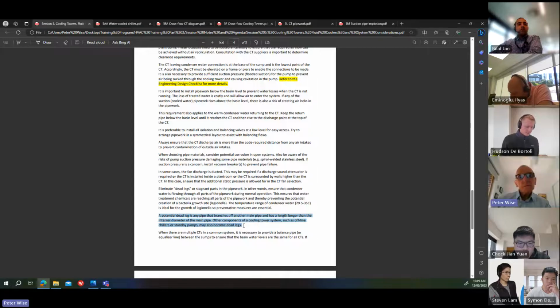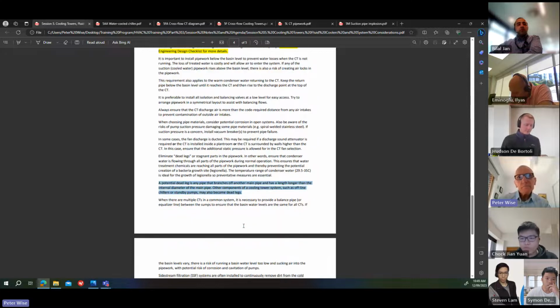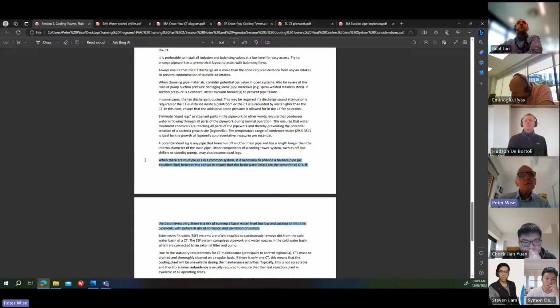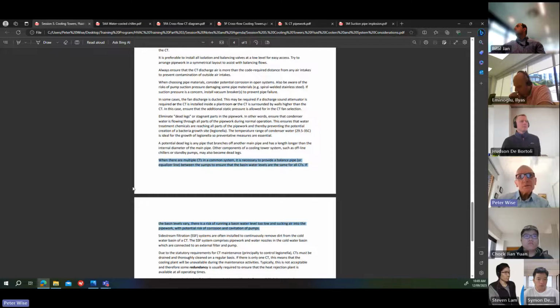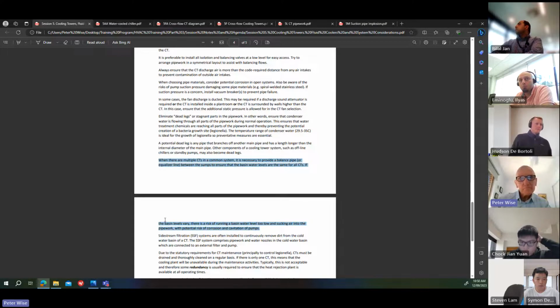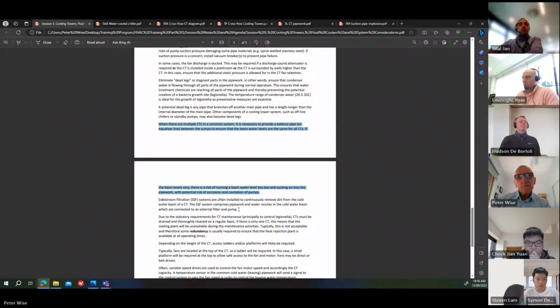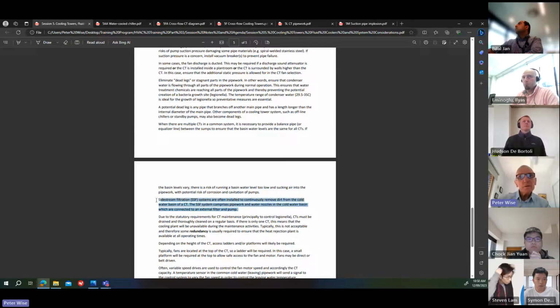Other components of a cooling tower system, such as offline chillers or standby pumps, may also become dead legs. So be aware of that as well. When we have multiple cooling towers in a common system, so they're all connected up to the same common pipework, it's necessary to provide a balance pipe, sometimes called an equaliser line. This goes between the sumps to ensure that the basin water levels are the same for all the cooling towers. If the basin levels vary, there's a risk of running a basin water level too low and sucking air into the pipework, with potential risk of corrosion and cavitation of pumps. So the equaliser line is there to ensure that those basin levels stay the same. It also depends on the balancing of the water returning to the cooling towers. So when you're commissioning cooling towers, you've got to get all those things right. Get the water flow to each tower even, and then you shouldn't have too many troubles.